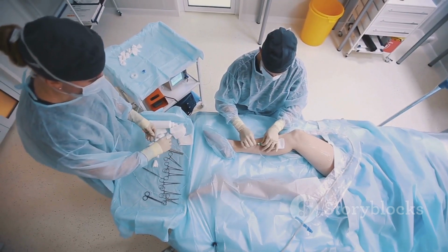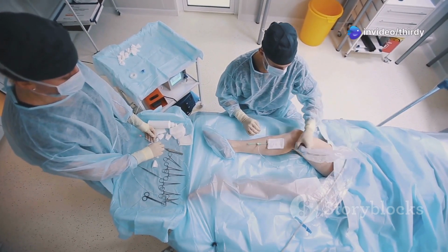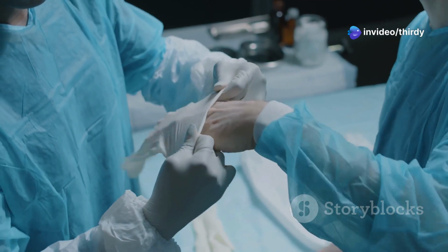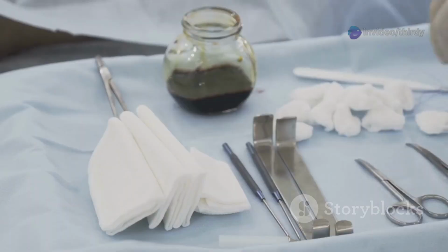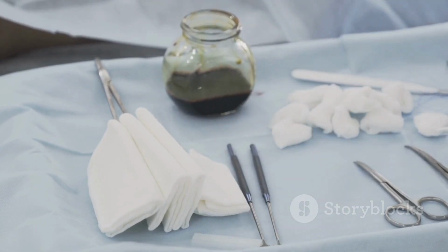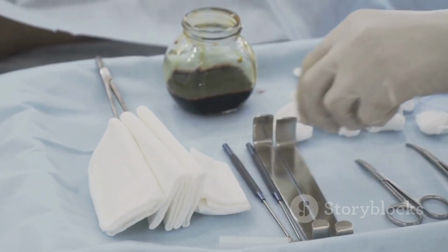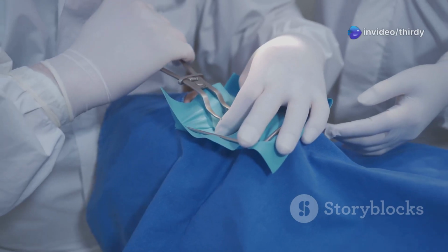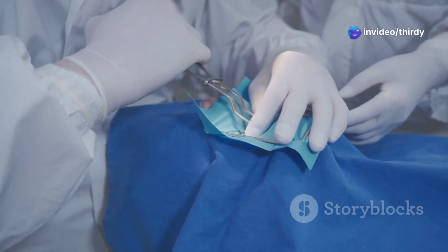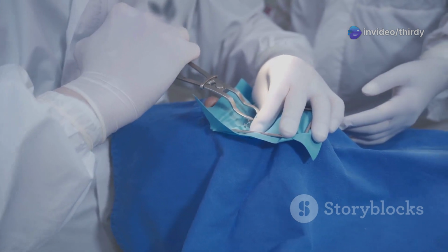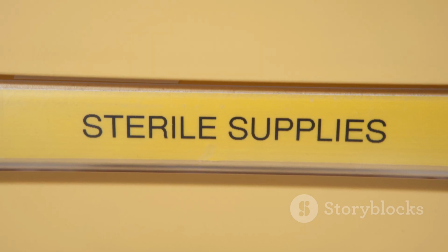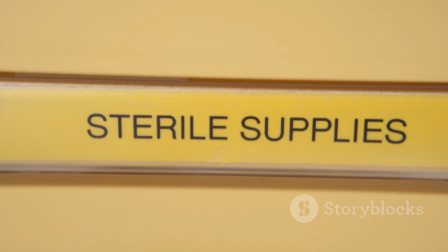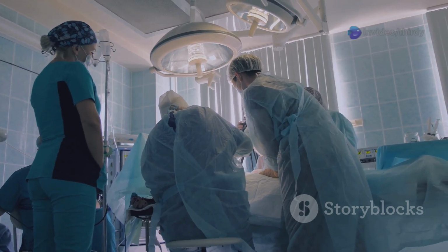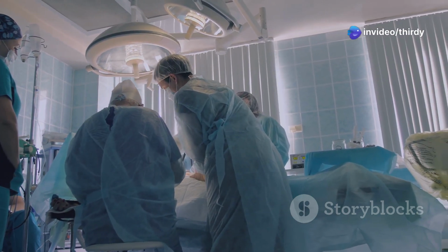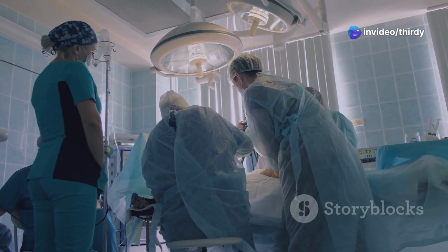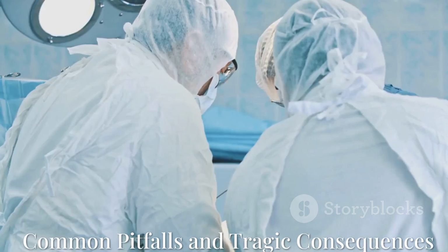Finally, after sterilization, the instruments must be handled and stored correctly to maintain their sterility until the moment they are needed in the operating room. They are packaged in special wraps or containers that allow the sterilant to penetrate but prevent microbes from getting in afterward. These packages are carefully inspected for any tears or moisture, as either could mean the barrier has been broken. Proper storage in a clean, dry, and controlled environment is the final link in this crucial chain. Skipping or rushing any of these steps, cleaning, disinfection, sterilization, and storage, is like leaving a door wide open for infection to walk right into the operating room.